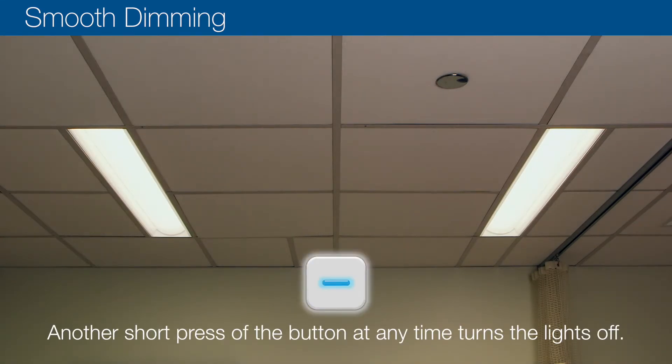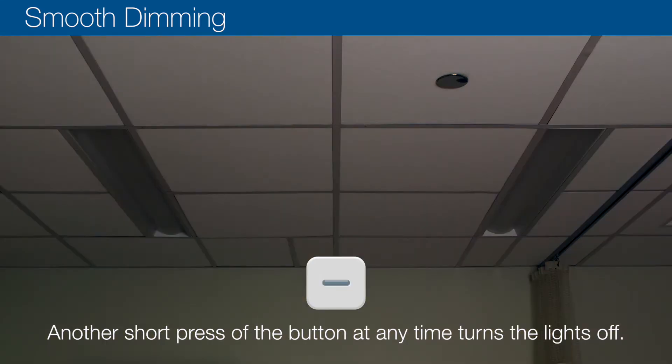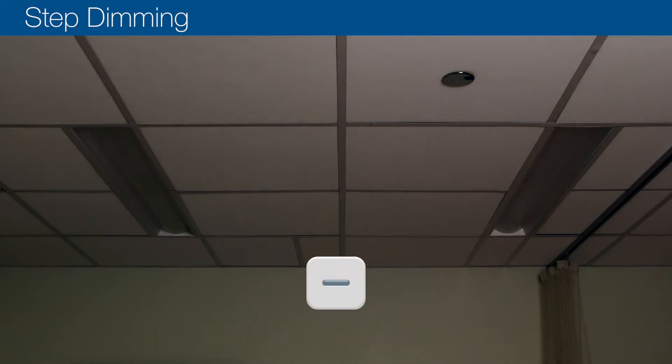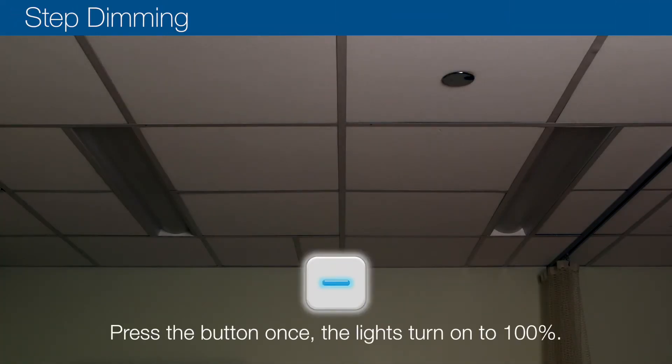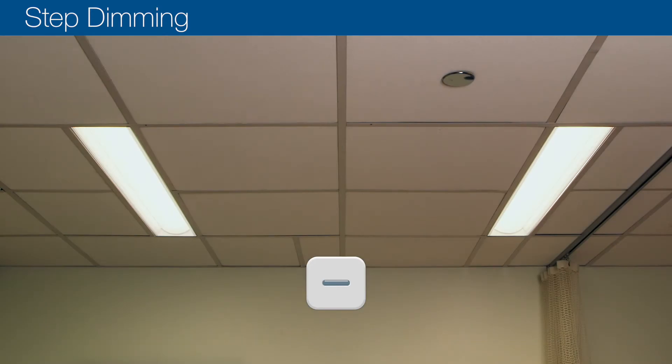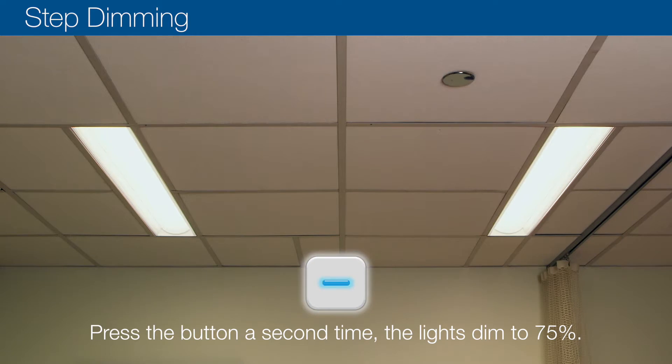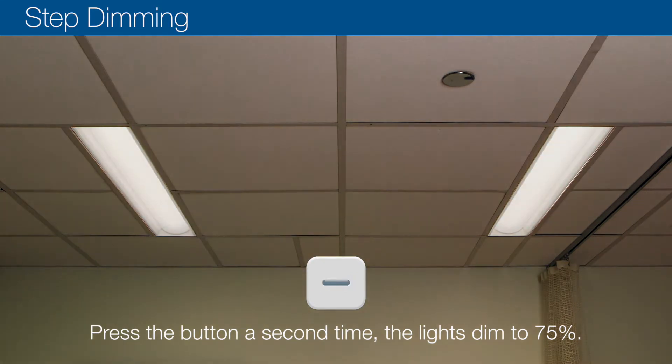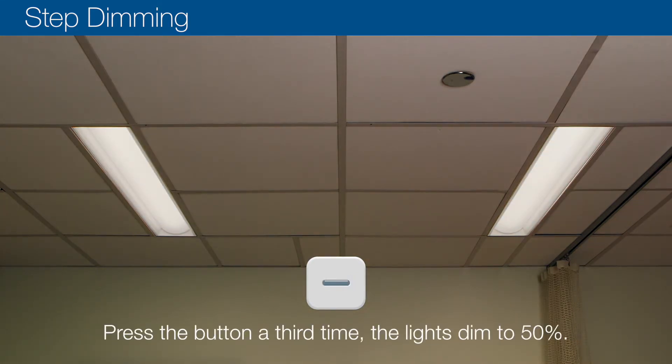Step dimming using the low voltage controller: press the button once, the lights turn on to 100%. Press the button a second time, the lights dim to 75%. Press the button a third time, the lights dim to 50%.